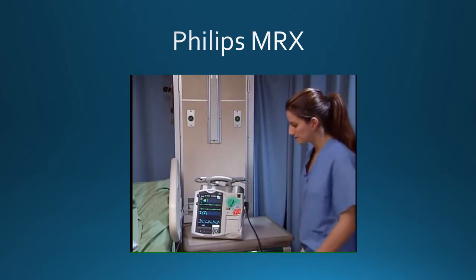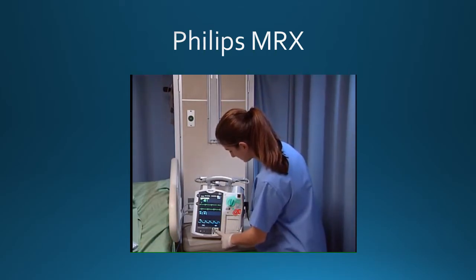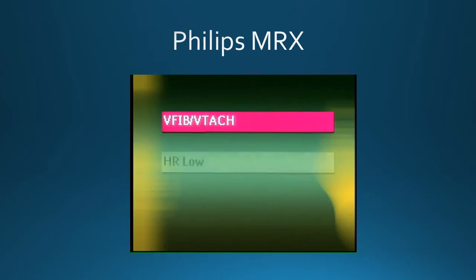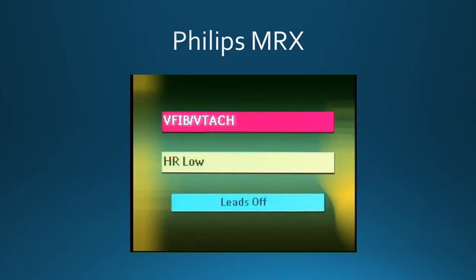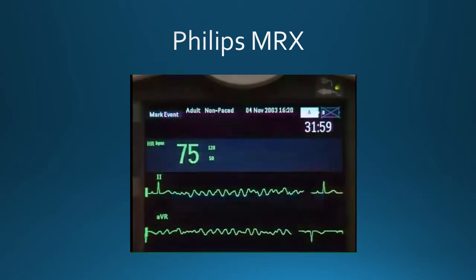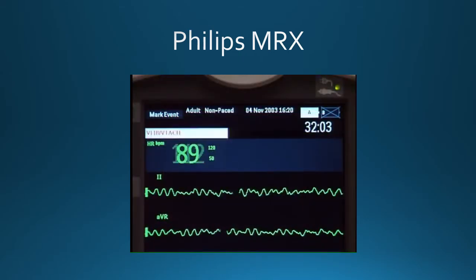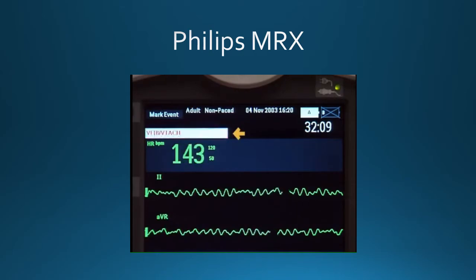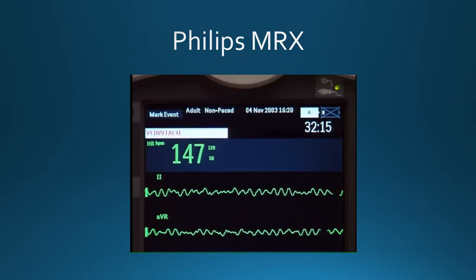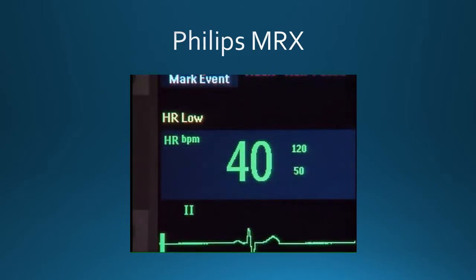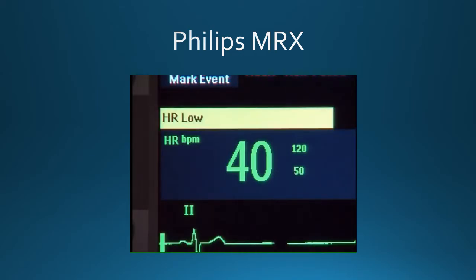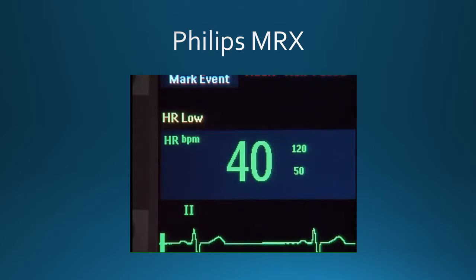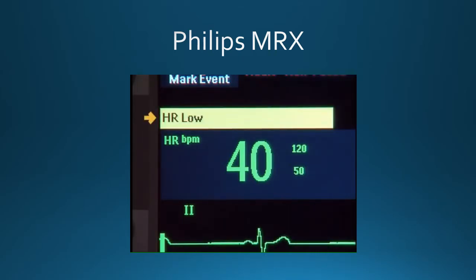With each measurement that the MRX monitors, there are alerts to advise when your patient's condition requires attention. Specifically, there are 3 alert levels: red alarm, yellow alarm, and inop message. A red alarm warns of a life-threatening condition, such as asystole or ventricular fibrillation. The cause of the alarm displays here with a red background and sounds like this. A yellow alarm indicates a non-life-threatening condition, such as when the heart rate measurement violates the high or low limits. The cause of the alarm displays with a yellow background and sounds like this.